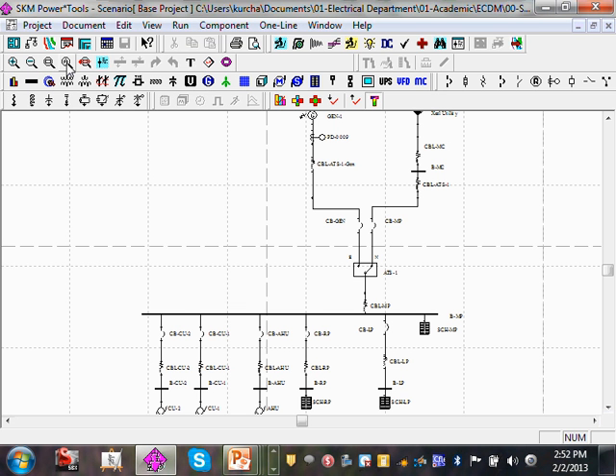So right here, when you go to short circuit calculation, I'm giving you some material to do by hand. You're going to call Xcel and say, hey, I'm at this location. Can you tell me what's the available short circuit right at this location of your distribution system? So you have to use Xcel's number. If you don't have Xcel's number, then we use what we call the infinite source. The infinite source is based on the transformer that they give you, 500 kVA. Find the full load current of the 500 kVA transformer, easy. What's the voltage? 480. Divided by the voltage, 1.73, and then divide it by the impedance of the transformer, which is typically from 3 to 6%. And you get yourself what? The available short circuit, the worst scenario available short circuit. That's called the infinite source.